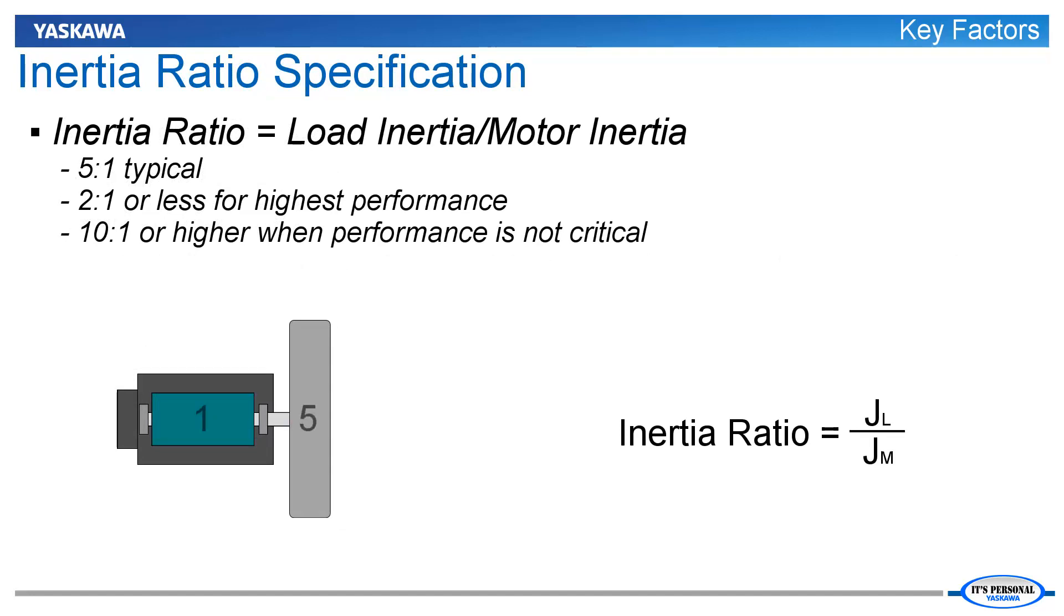Inertia ratios around 5 to 1 are typical for many applications. Performance tends to go up as the inertia ratio is lowered, often down to 2 to 1, 1 to 1, or lower.